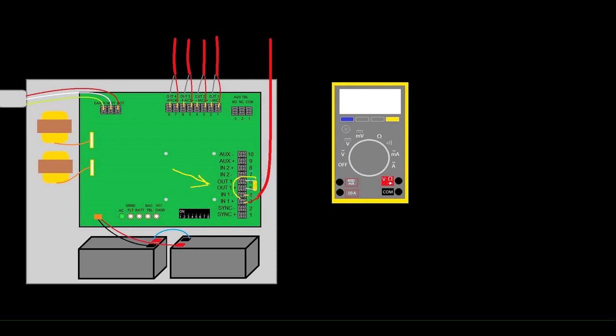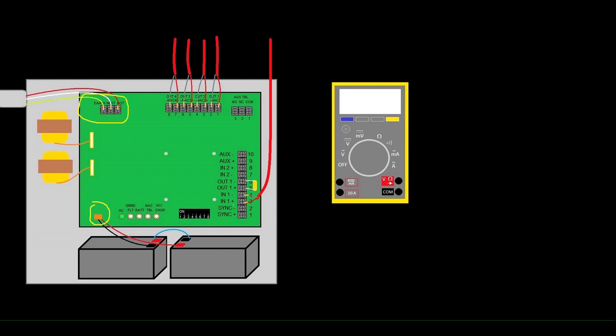So this resistor here that I circled has nothing to do with the FCPS. This power supply does not care if that resistor exists or doesn't. That's for the circuit that's triggering it. So whether you have an open circuit, whether you lose AC power, whether you lose battery power, any of those troubles is going to trigger and is going to cause an open circuit on your trigger.